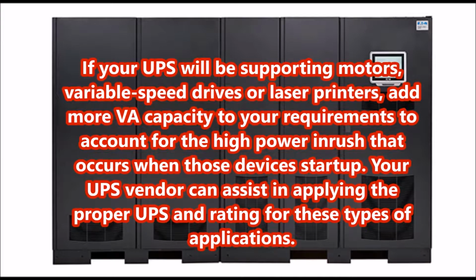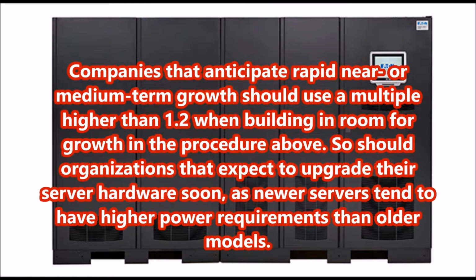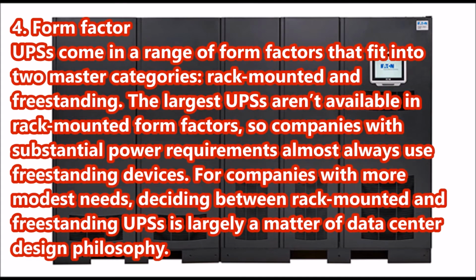If your UPS will be supporting motors, variable speed drives or laser printers, add more VA capacity to your requirements to account for the high power inrush that occurs when those devices start up. Your UPS vendor can assist in applying the proper UPS and rating for these types of applications. Companies that anticipate rapid near or medium-term growth should use a multiple higher than 1.2 when building in room for growth in the procedure above. So should organizations that expect to upgrade their server hardware soon, as newer servers tend to have higher power requirements than older models.